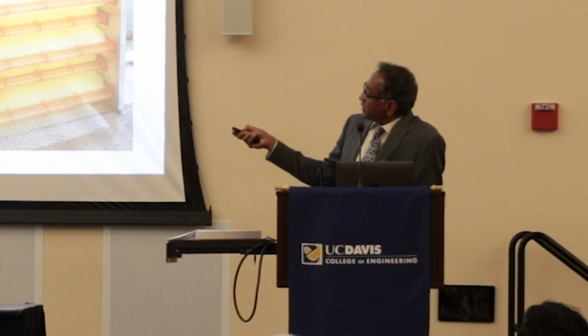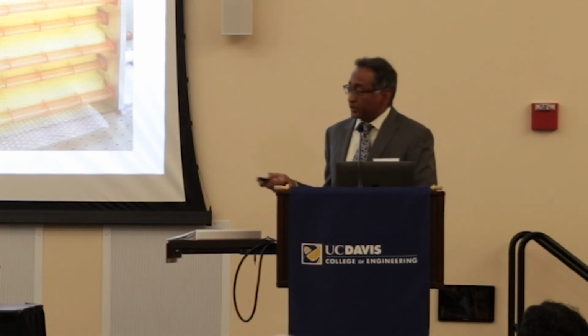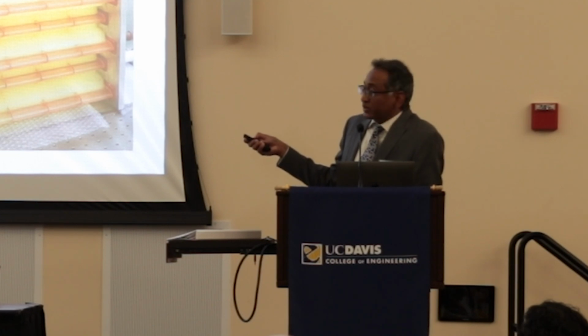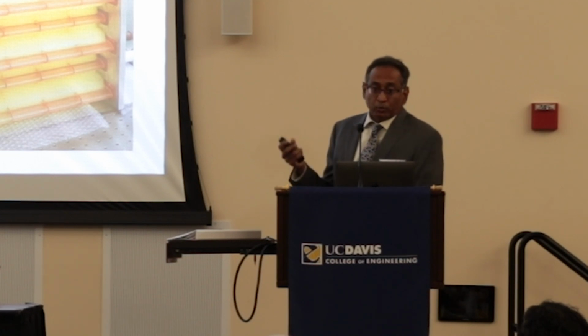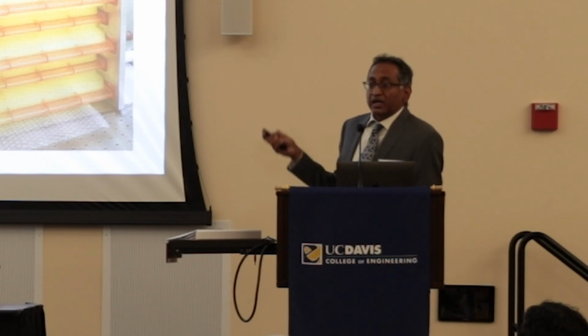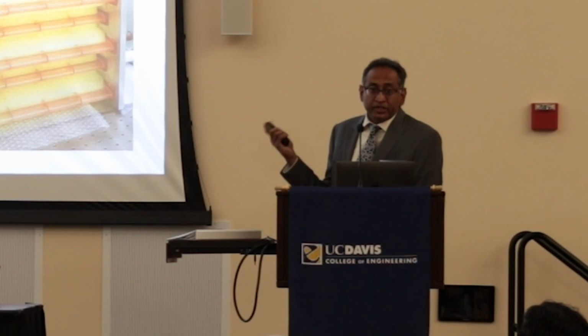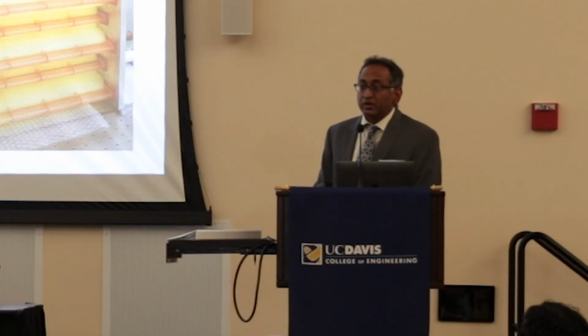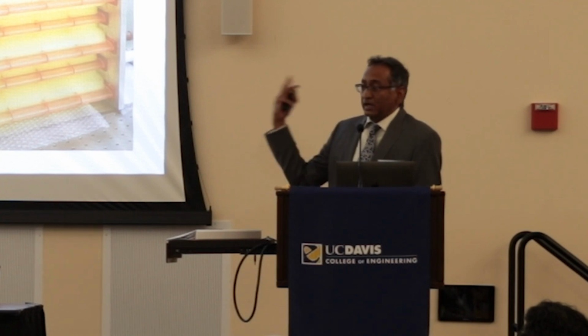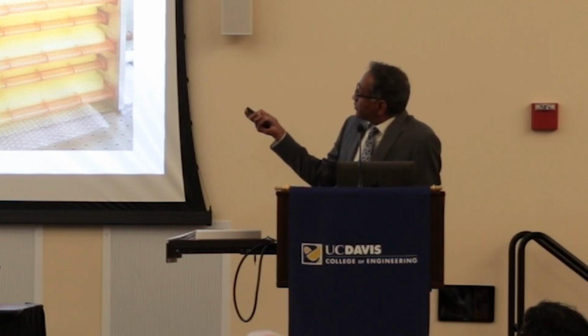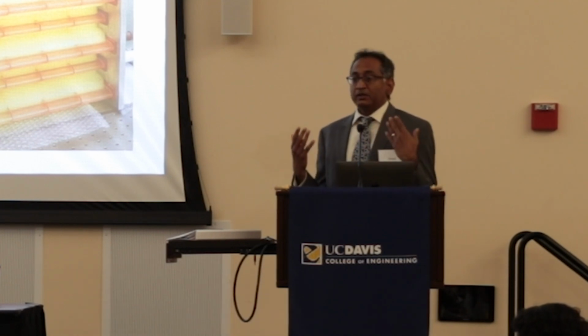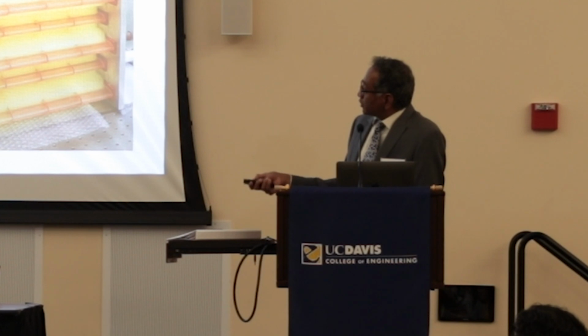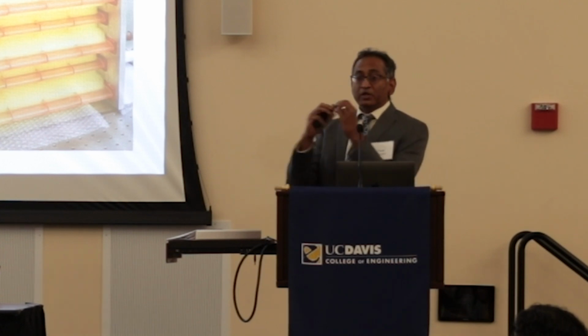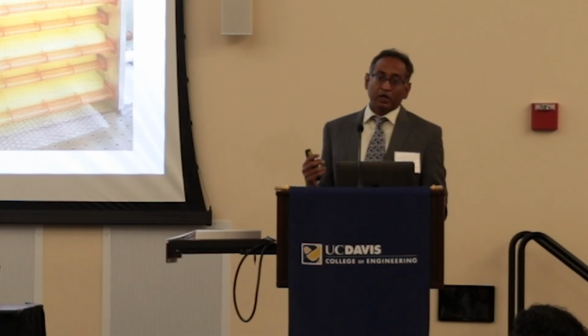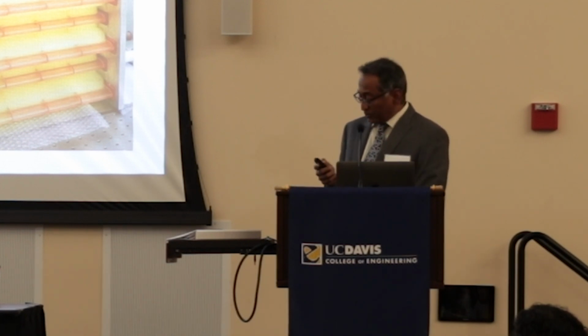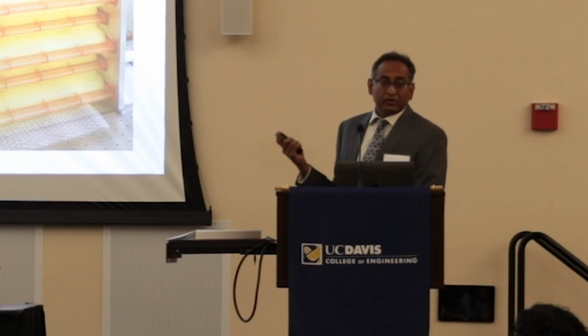What I mean by that is you contain the propane refrigerant inside the heat pump, it comes factory sealed, and then you have a secondary loop where the propane exchanges heat or cooling with the secondary loop, like glycol water, and that flows into an air handler and provides the heating or cooling to the house. The tension here is that the secondary loop adds inefficiencies and you lose performance because of the additional heat exchangers in the process. We have looked at this tension and at a solution for it. The biggest bottleneck in the secondary loop is that you're using heat exchangers like what is shown here. Basically a bunch of tubes and fins that you blow air across, with the glycol water going through the tubes. And this has been in business for decades. Industry makes this all the time.